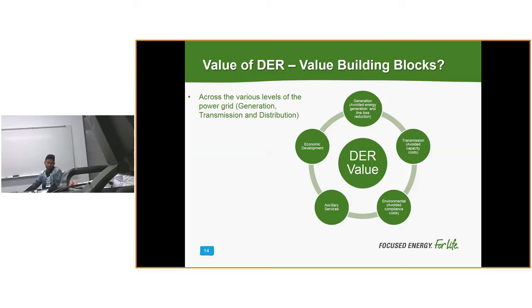You asked about the dynamic response of energy storage, right? Its response is extremely fast to these types of events compared to a power plant. A power plant takes maybe 15, 20, 30 seconds to respond to an AGC signal. A battery could respond under 4 seconds to an AGC signal—it can go even faster than that, but within that range.